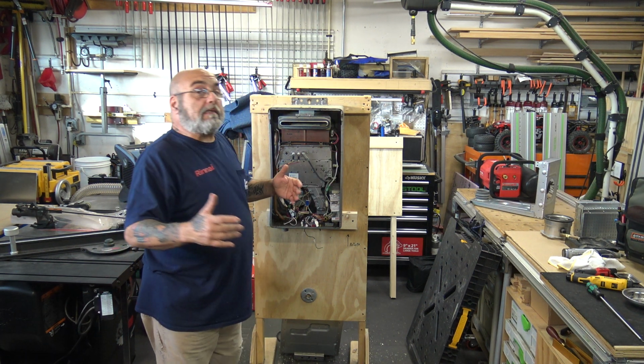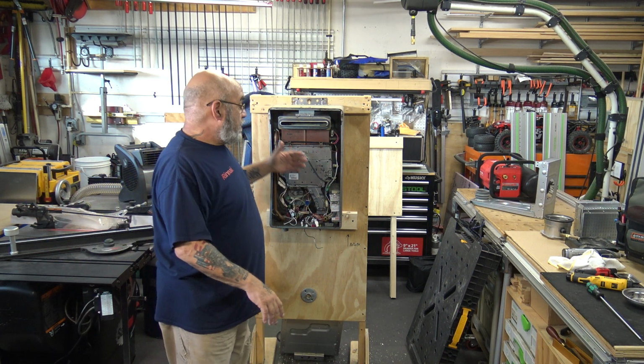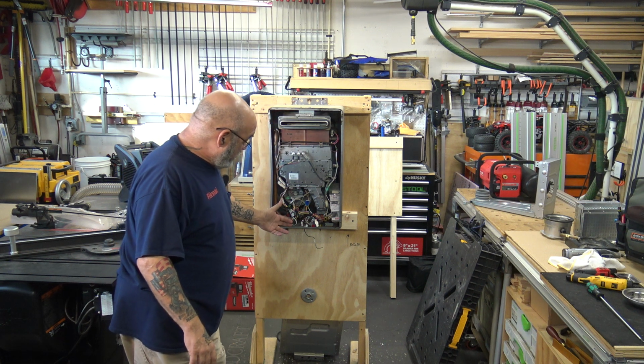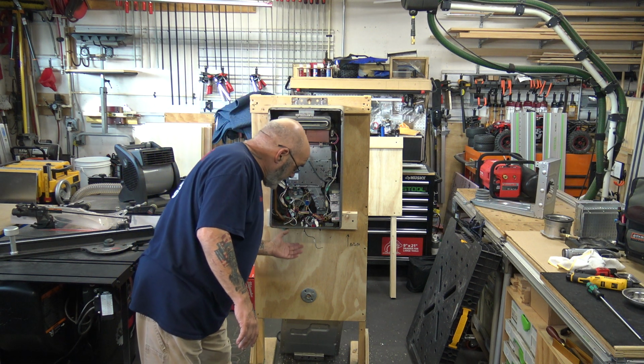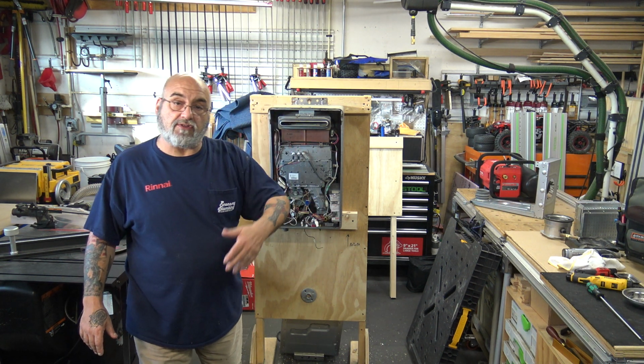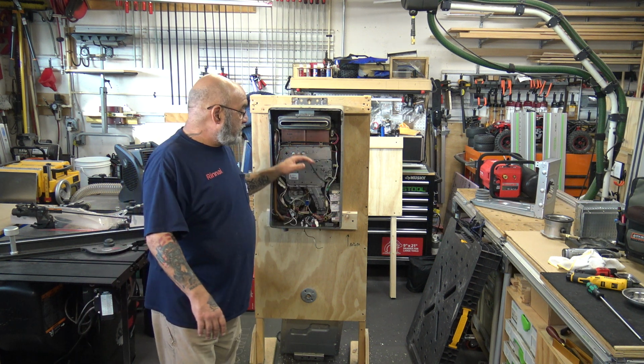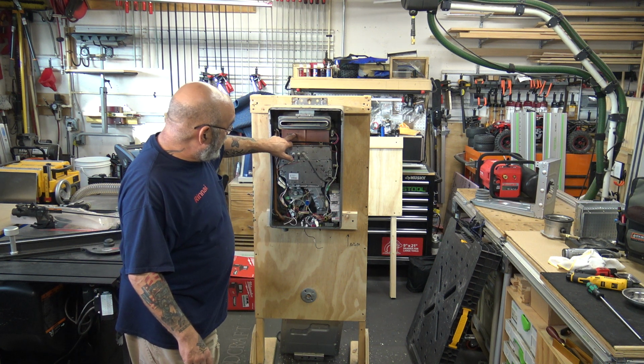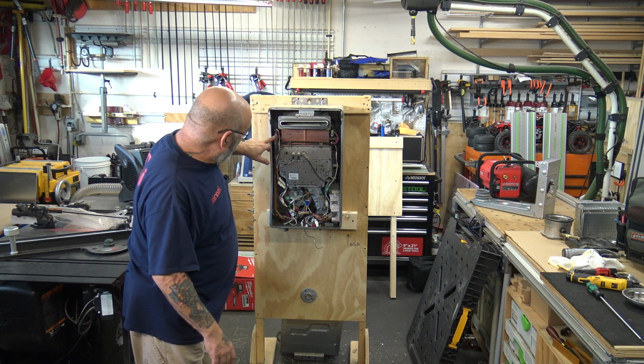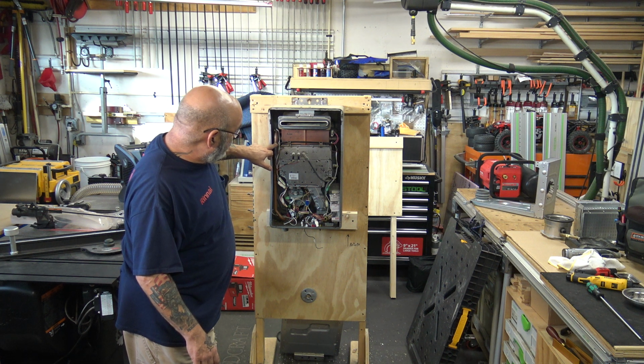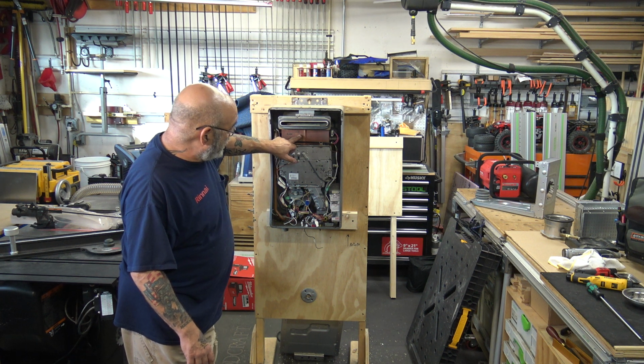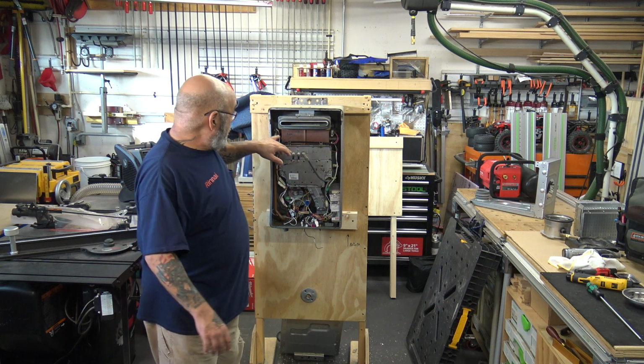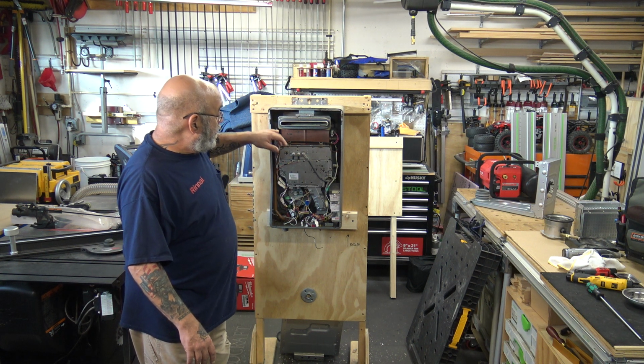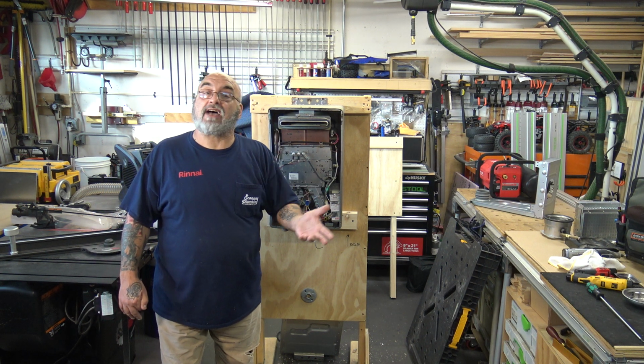So basically what's happening: you're getting a leak into the chassis, most likely out, either on the ground or inside the house, and something within the heat exchanger, either the tubing, the hot cold water feed, the mix, the actual heat exchanger, or the thermistor has formed some type of hole.